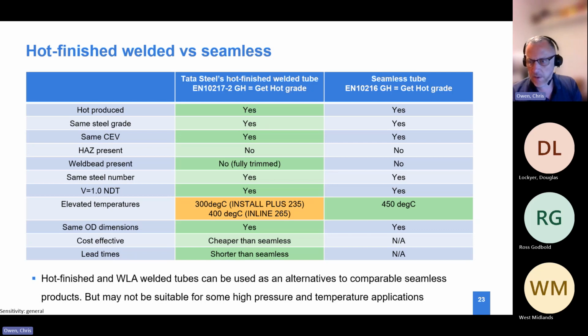Other than temperatures in excess of 400 degrees C, we'd be fine for most applications. Same manufacturing process in terms of testing, same CEV, the carbon equivalent value, same steel grade, so they're interchangeable in most applications within building services where we're looking at maybe up to a maximum of 300 or 400 degrees C. And certainly for pressures, we can go almost 50, 60, 70, 80, 90 bar, depending on the size of the tube and how it's jointed, which we'll talk about later.